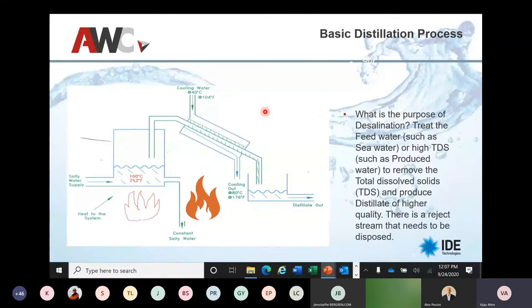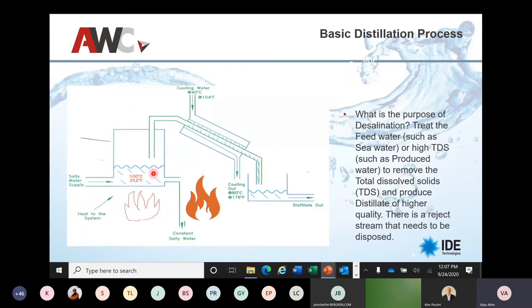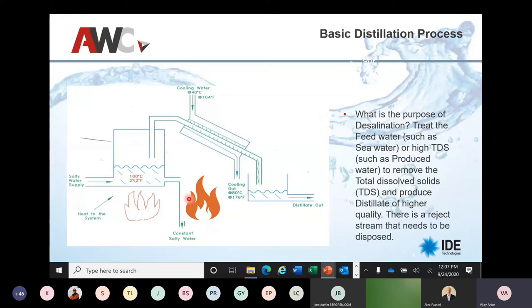What is the purpose of desalination? We need to treat feed water such as seawater or high TDS water. For instance, we can use reverse osmosis up to about 40,000–45,000 ppm TDS, but beyond that, what's the technology? That's where thermal technology comes into picture. We have a feed water, we need to treat it to remove the TDS — heat the water to 100°C to boil it, then cool or condense it and we get distilled water. There is a brine stream coming out which is highly concentrated and needs disposal.